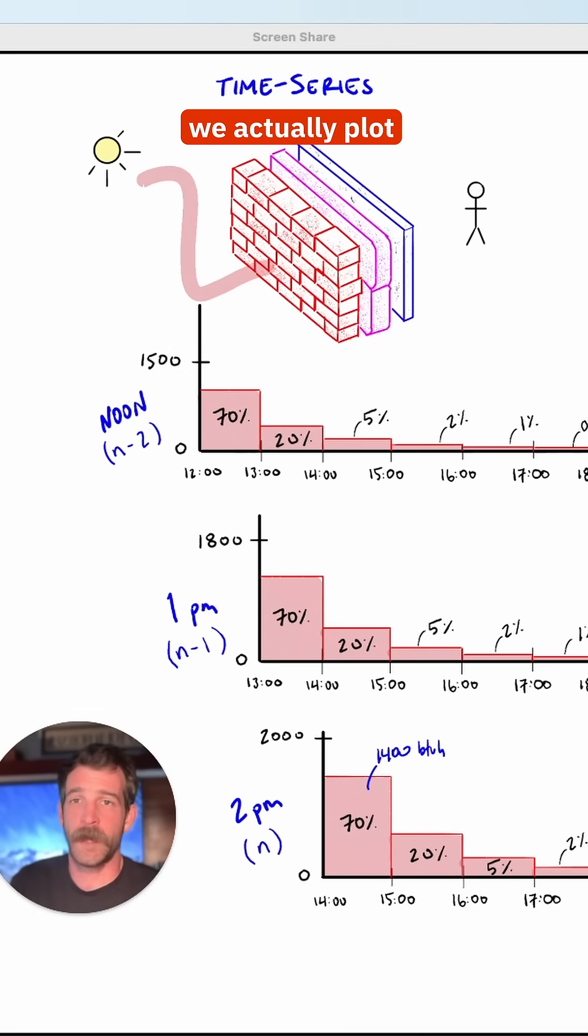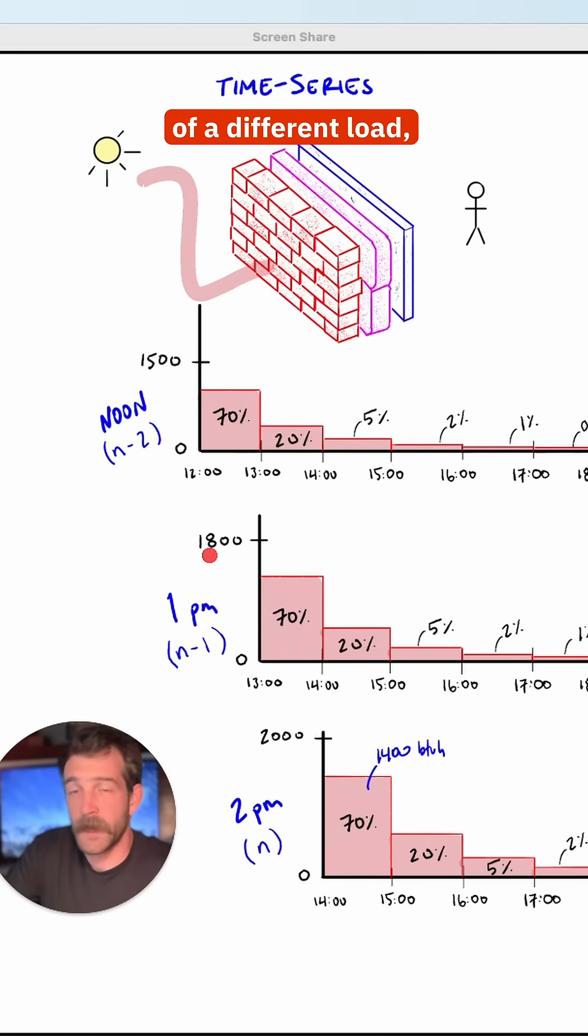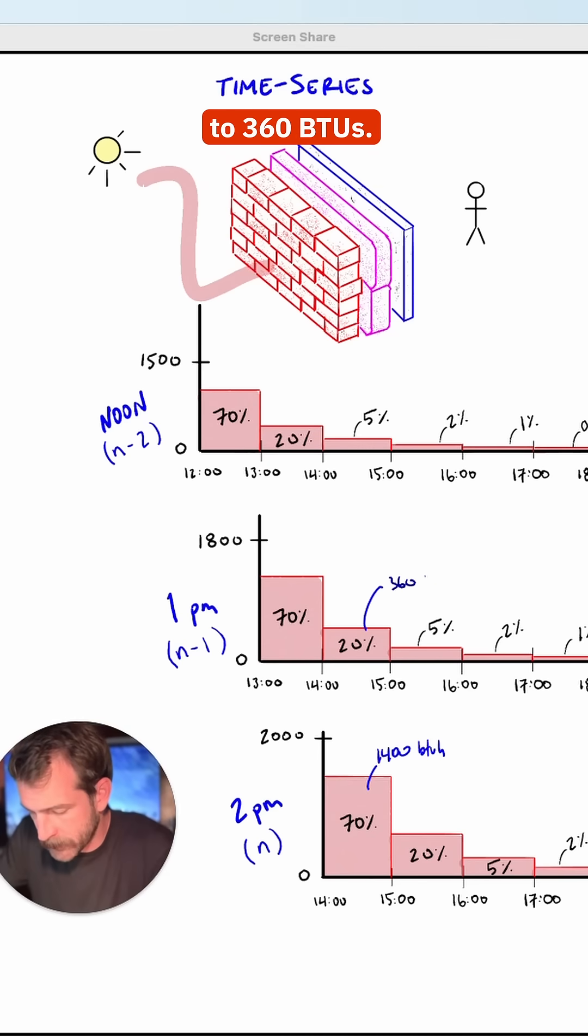And when we calculate using time series, we actually plot this out a full 24 hours previous to the hour for which we're calculating load. So if I'm calculating for 2 p.m., now I go back an hour, and it's not the same instantaneous load. The load was different at 1 p.m. So I'm going to take 20% of a different load, which comes out to 360 BTUs.